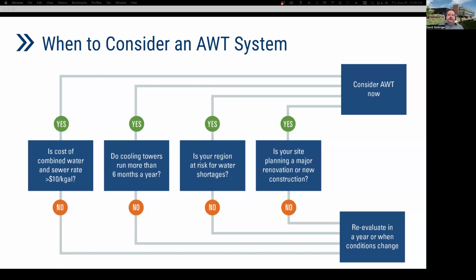The questions shown in this flow chart can help determine if an AWT system will be cost-effective for your facility. If you answer yes to any of these questions, I recommend that you consider an AWT system now. If you answer no, you might want to reevaluate in a year or if conditions change significantly. The 4 questions are, is the cost of combined water and sewer rate greater than $10 per 1,000 gallons? Do your cooling towers run more than 6 months out of a year? I mentioned our data center application where we have cooling towers that can run year round. So significant opportunity for water savings.